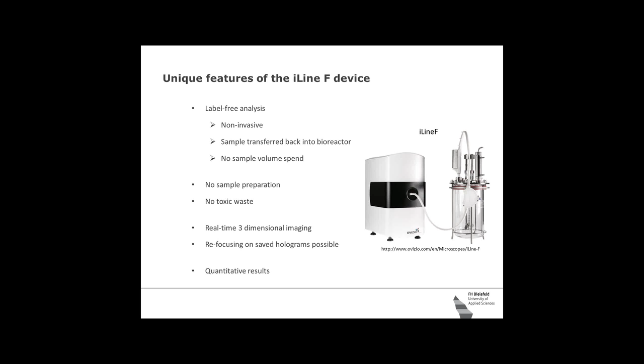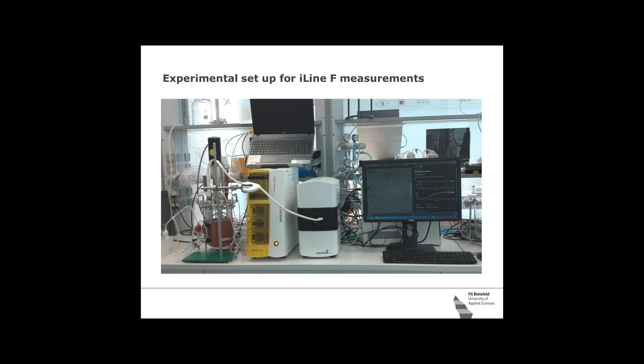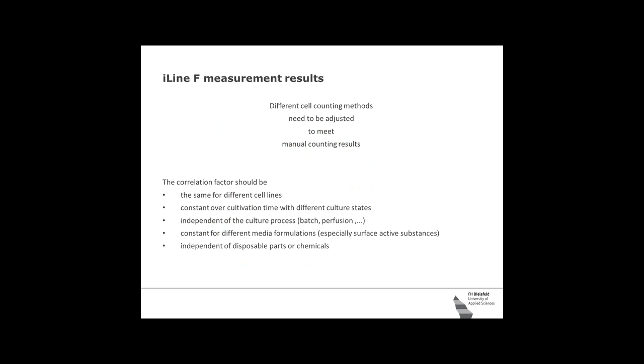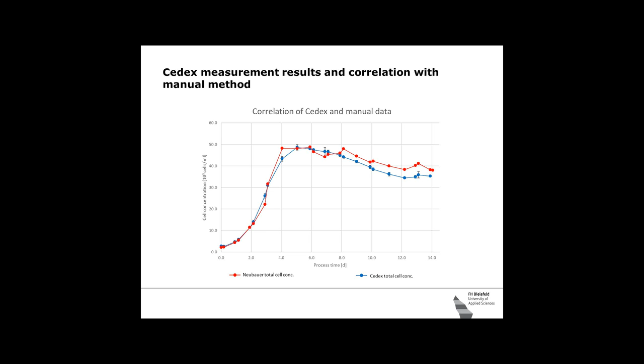The connection between the bioreactor and the measurement, the analytical unit where the hologram is generated, that's a disposable part. And the customer should expect that replacing a disposable part and starting a new process should give the same results if we have one correlation factor, and it should not change the correlation factor. Here you can see the correlation between Cedex and manual data using a factor that's usually 0.83, 0.85 or something like that. For whatever reason, it is there, but if you multiply the results with this factor, you get the same also over a long period of time.